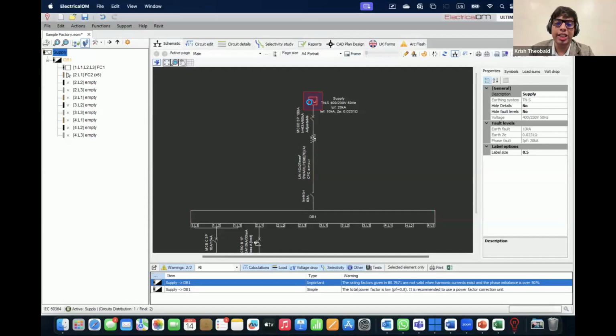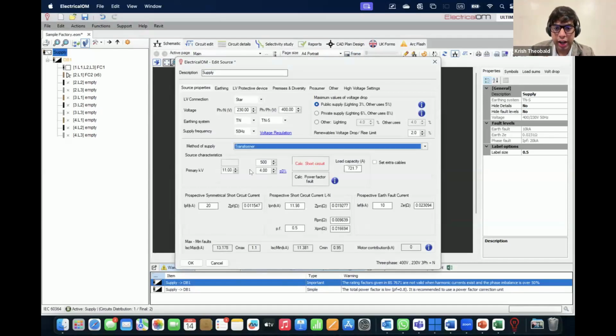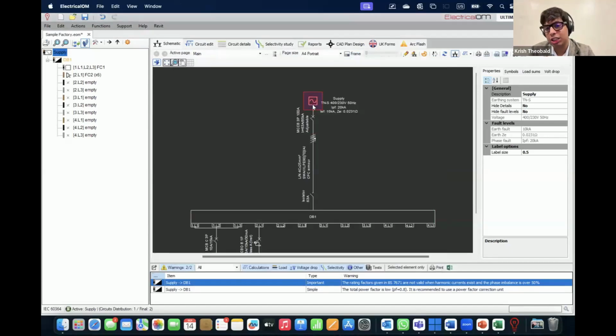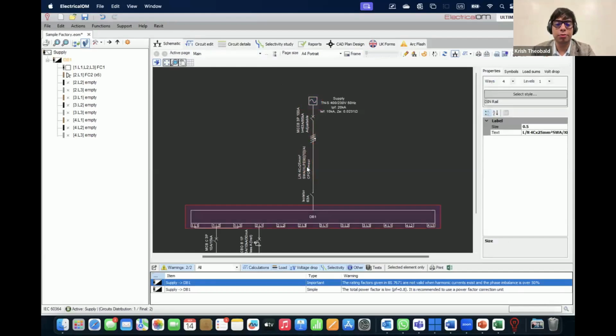Say, for example, I have a transformer, and these are the transformer characteristics. I have a fault current contribution of this transformer. If it is a low voltage supply, I have measured the earth fault loop impedance and the respective short circuit current, so I know what its contribution is. How does it calculate minimum fault current? It says I have a cable of this length, this is the resistivity of the cable, this is the reactive component of the impedance, this is the temperature of the conductor, and then this is the fault current.